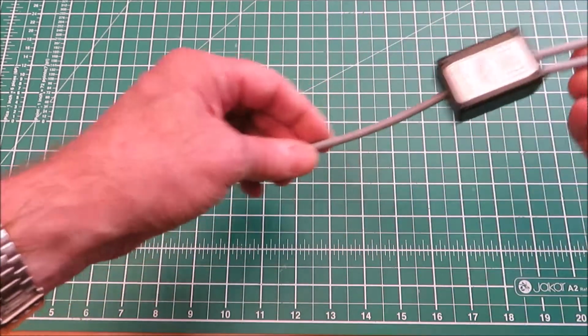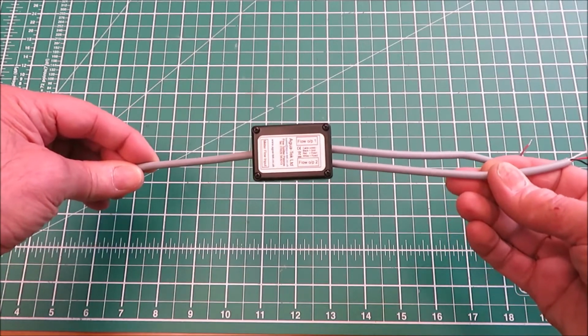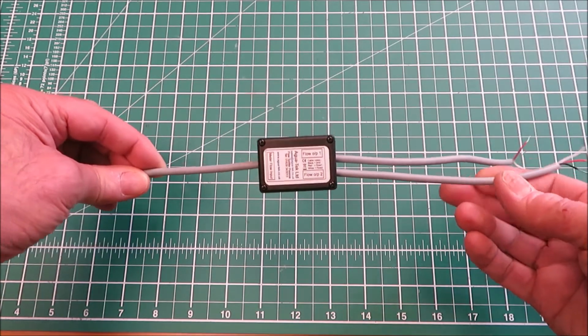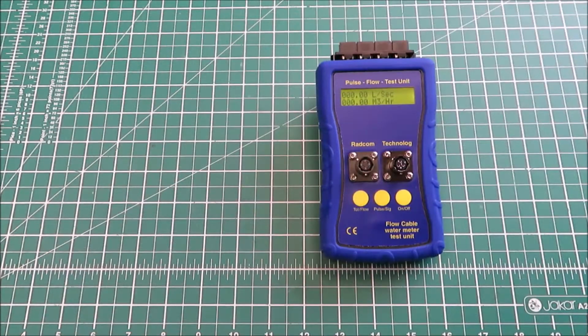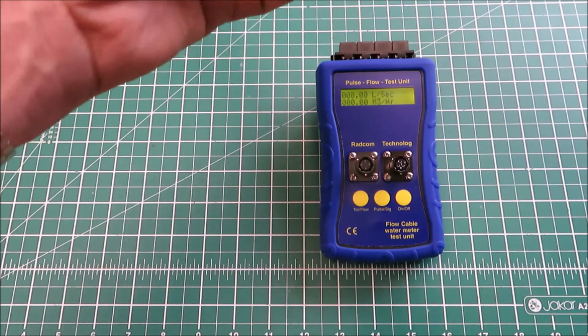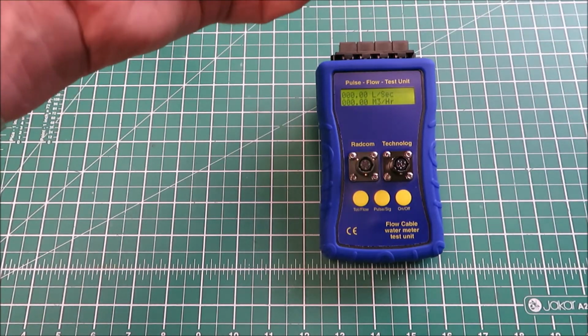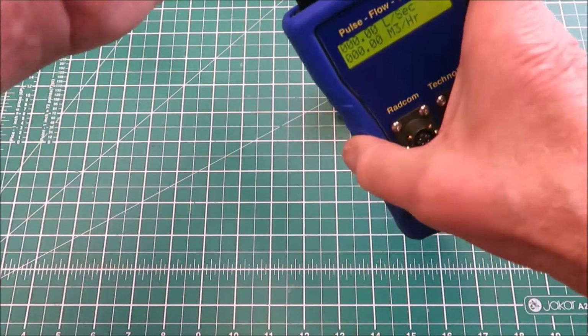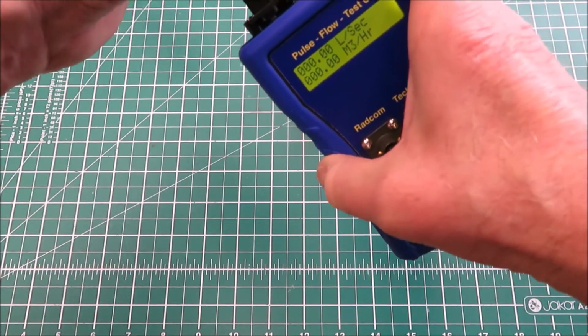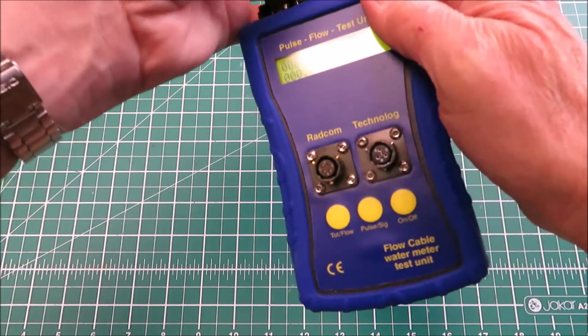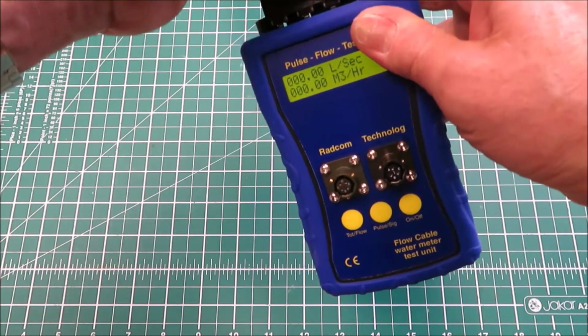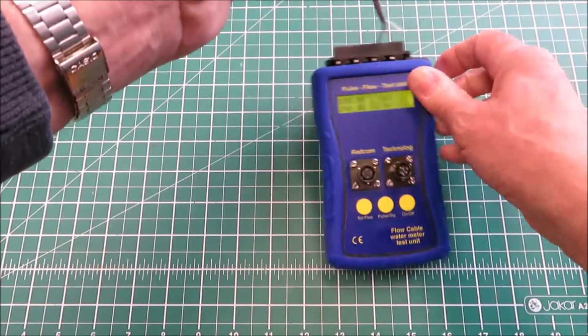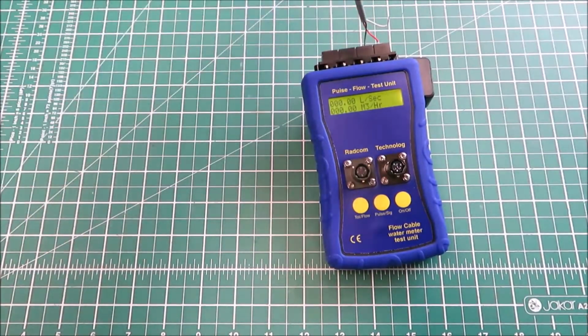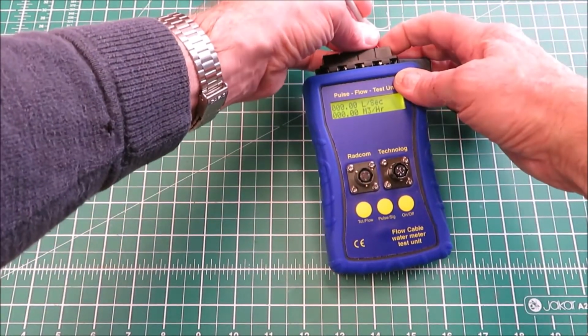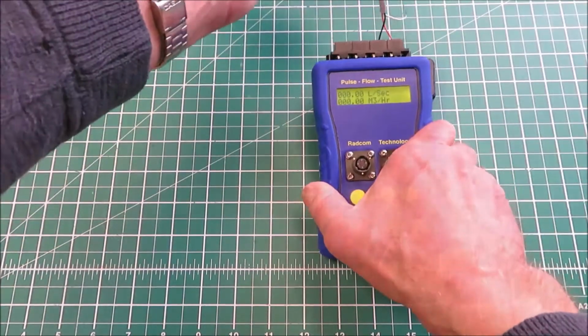So I'm going to demonstrate how to test this unit using a pulse test unit. Now I've got the pulse test unit switched on, so that you can see the display. If I take one of the outputs, I'll use the black and red. I just connect those into the input of the pulse test unit. So black to black, red to red. I could have used the white wire there, black and white, but I've used the red. Just making sure that that's in properly. Level it up a little bit.